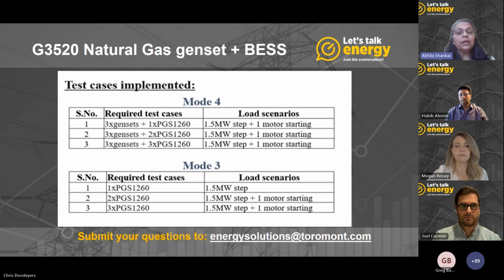Okay, here you will see that the CAT analysis was done in two different tests. In the mode 4 test case, three 2.5 megawatt standby rated natural gas gensets were subjected to the first step of 1.5 megawatt, and in the second step, an 800 horsepower motor was started.